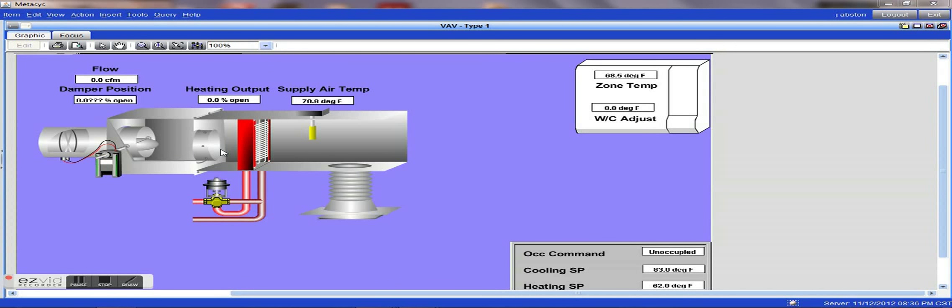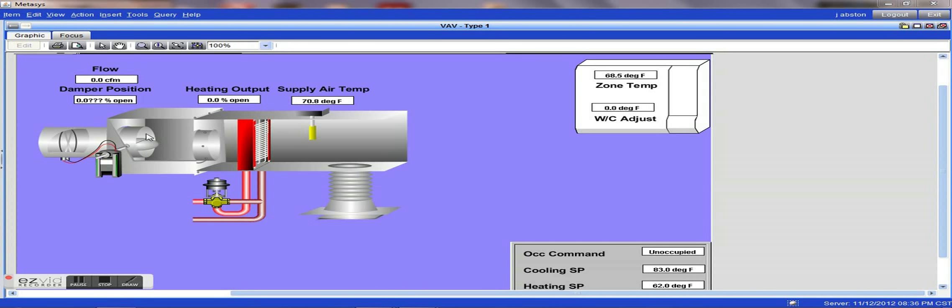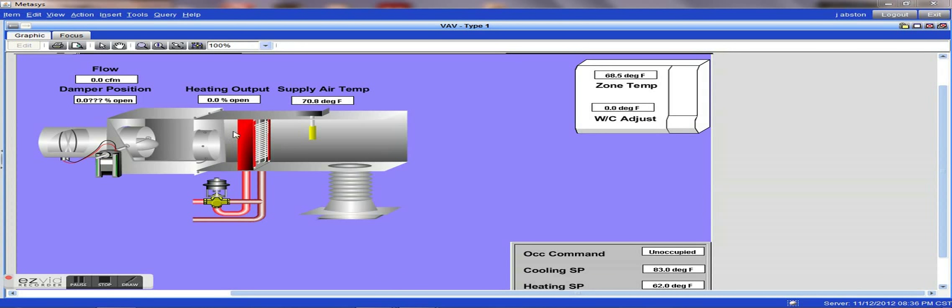When the space calls for heating, the VAV actuator will generally close down, slow down the air flow, and will allow the air to pick up some of the heat from the coil.